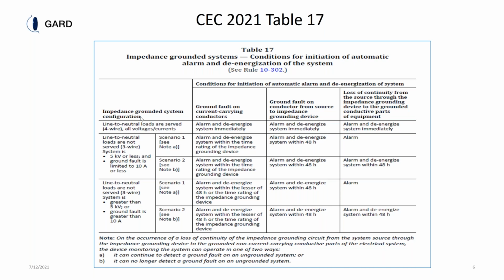But there are three different systems you need to monitor. One is where line to neutral loads are served. Unfortunately, Canada allows line to neutral loads to be served on high impedance grounded systems, and we don't think it's a good idea. But if anything happens, you have to de-energize immediately. Second is where line to neutral loads are not served, and your system is 5 kV or less, and the ground fault current is limited to 10 amps or less. In which case, two different scenarios come about.